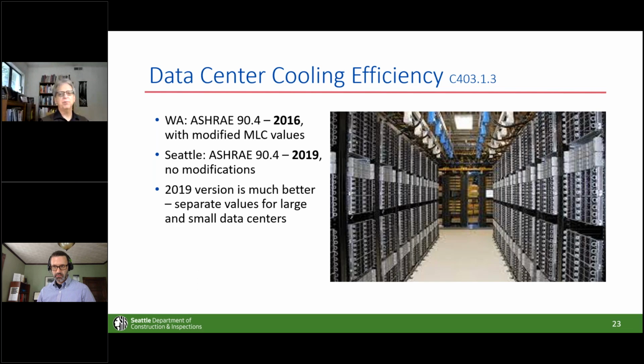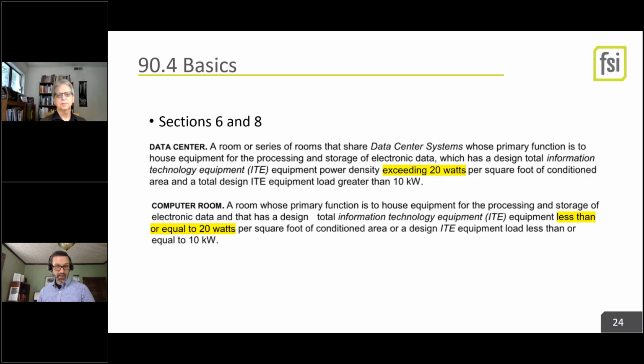You might ask yourself, what counts as a large or small data center, and what's just a computer room? The magic line is 20 watts per square foot. So even small data rooms in office buildings can, in some ways, meet that data center requirement. It's a thing to be aware of as you get into it.